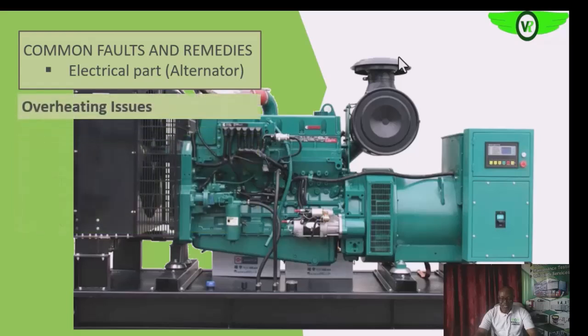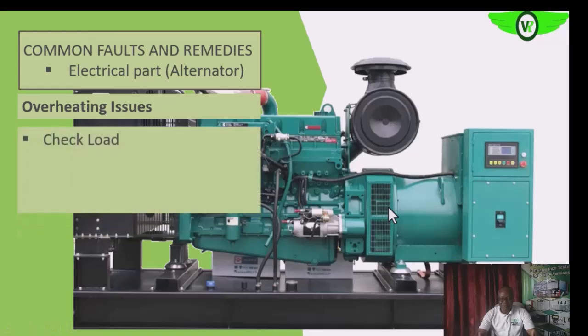During operation, the alternator could be overheating. When we have overheating issues, a possible cause is overloading. The load is seen as current at the alternator — once excessive current flows through the armature winding, the I-squared-R effect generates heat. Once it goes beyond what is normal, the heat becomes too excessive and any cooling system around the alternator will no longer be effective.